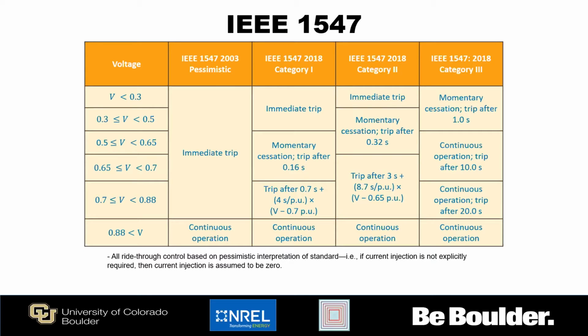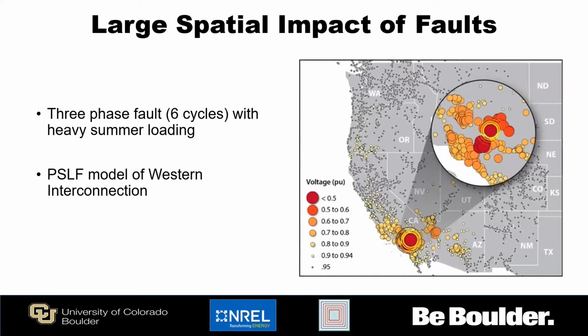However, it's now been revised a couple times, and the latest revision is IEEE 1547-2018, and this allows for basically 3 different categories of ride-through compliance. You see here Category 1, Category 2, and Category 3, and the goal here is, because we now have larger amounts of this distributed generation, we expect it to play a role in continuing to maintain system operations. And specifically, we want to look here at what is the impact when there are large faults in the system.